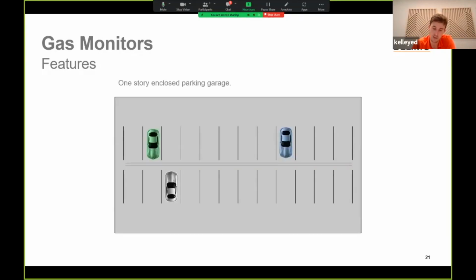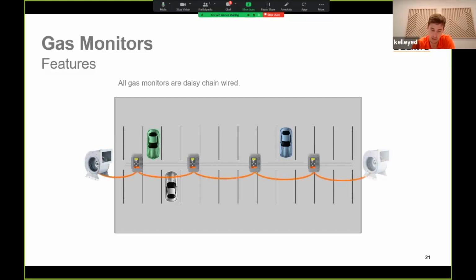So this is an example. Let's say you have a 1-story enclosed parking garage. You have an intake fan to bring in fresh air and an exhaust fan to exhaust the bad air. And you follow the Belimo guidelines, and you have 4 gas monitors to correctly monitor the space. All gas monitors are wired daisy chain for up to 32 devices. In this application, you have 2 fans, both on off, so you only need 2 relays. You can do this 1 of 2 ways. You can have 1 B that has 2 relays, the rest Cs, or 2 Bs and the middle 2 Cs. So we decided to use 2 Bs because we figured it might be more cost effective for wiring.